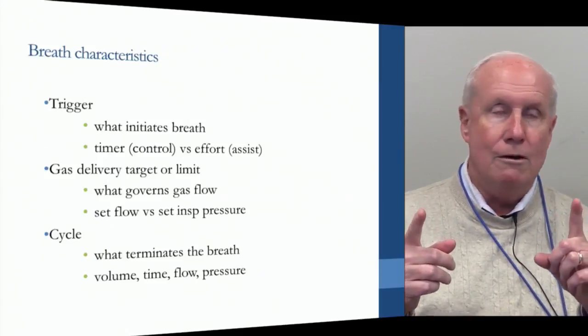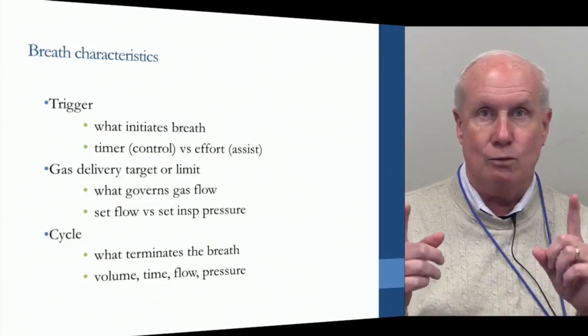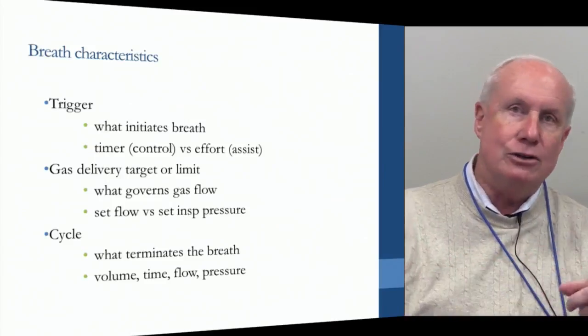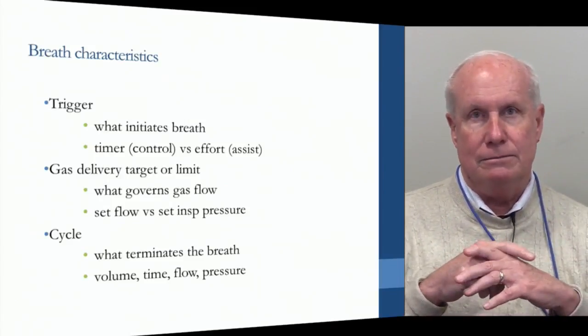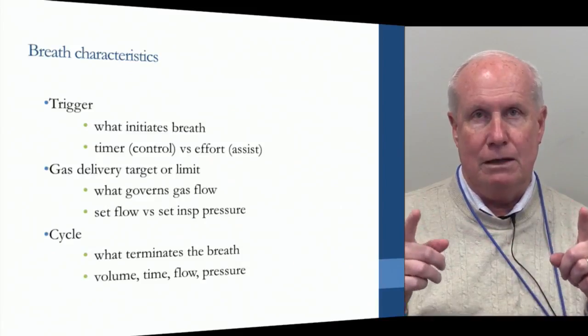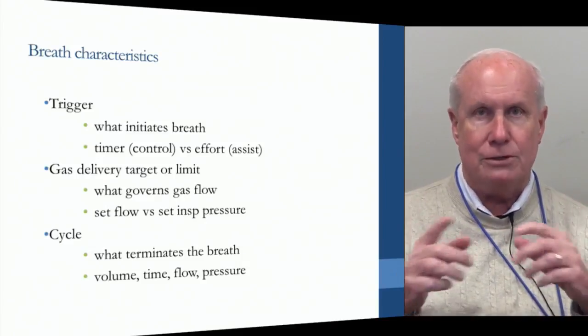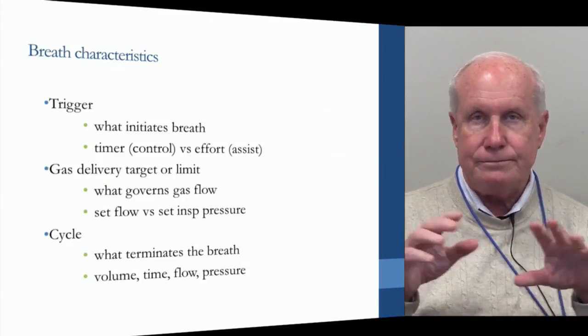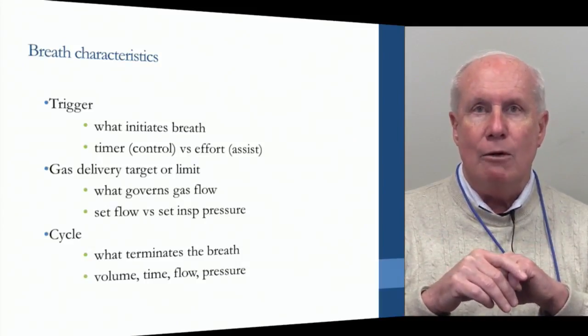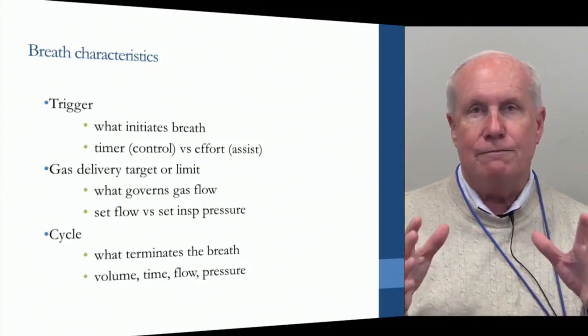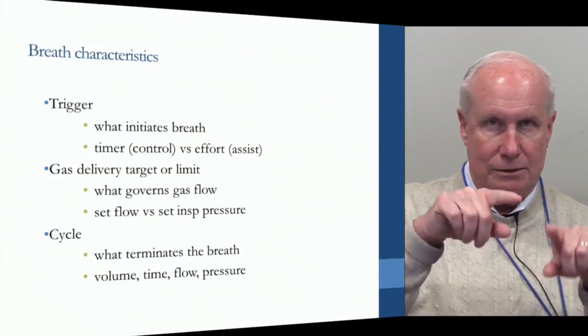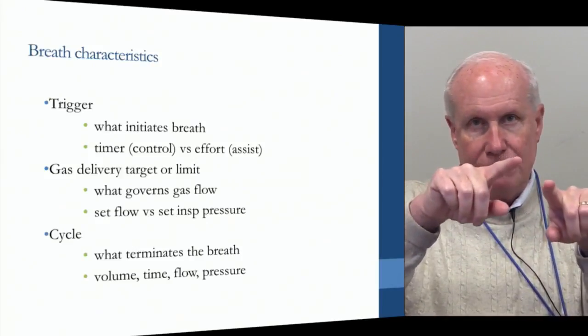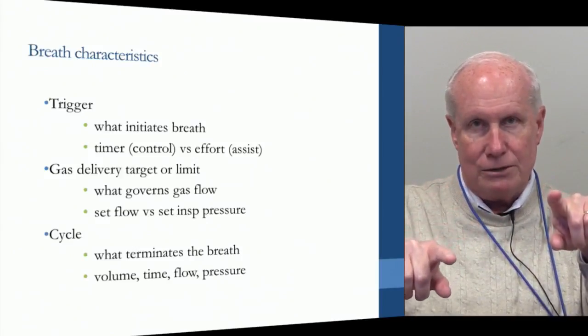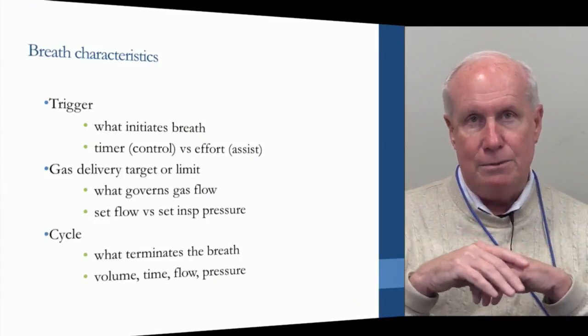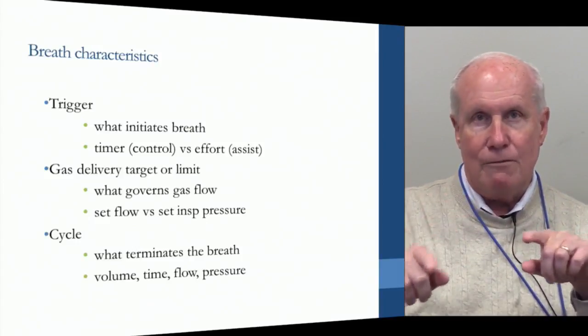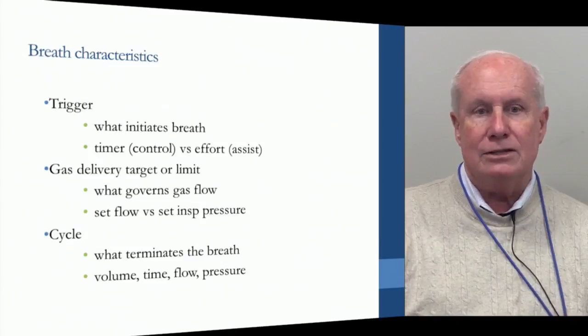Deliver the breath for 0.6 seconds, 0.8 seconds, 1.0 seconds. And that's usually linked to the pressure flow algorithm, or the pressure breath delivery algorithm. And finally, with the pressure support breath, it's a flow cycling mechanism. In other words, you set a pressure, and then as the lung fills, the driving pressure falls because the lung is being stretched. The flow tails off, and when it reaches a certain minimum, it cycles off.